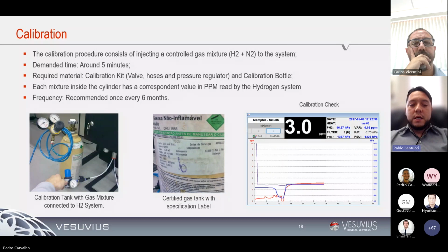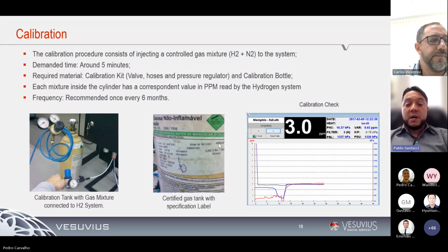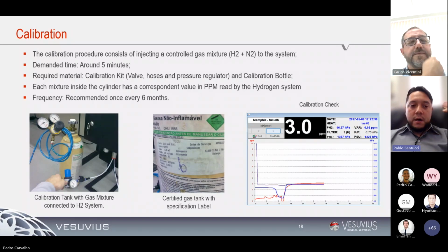So that's what the theory says in terms of reference for calibration. And the frequency of this procedure depends from customer to customer, but I would say for most of the guys in the Southern Hemisphere, where room temperature will not change much, you could consider a calibration procedure every 6 months, whereas for countries or plants in the Northern Hemisphere, where the room temperature tends to change a little bit more, I would say every single season. So every 4 months, 3 months, it would be recommended.